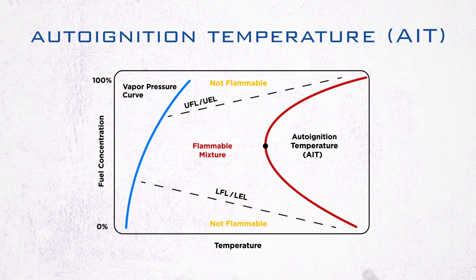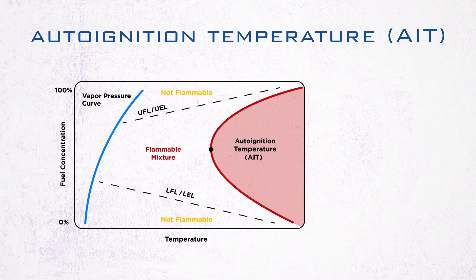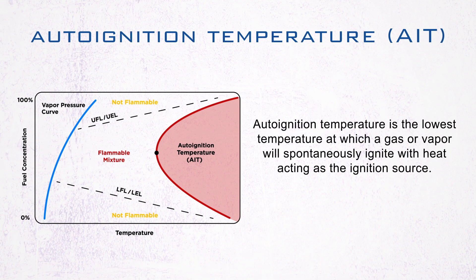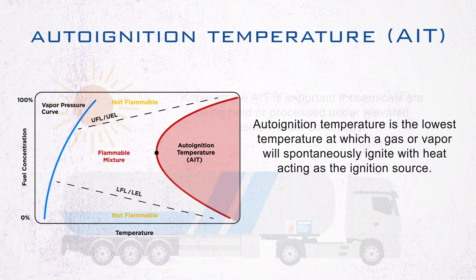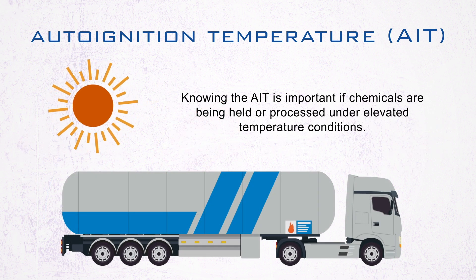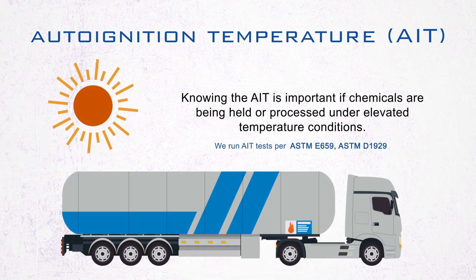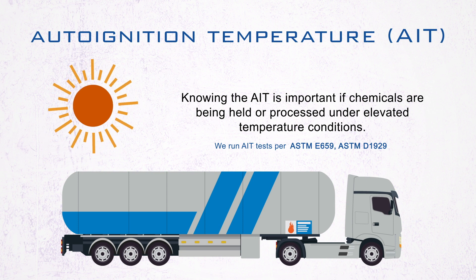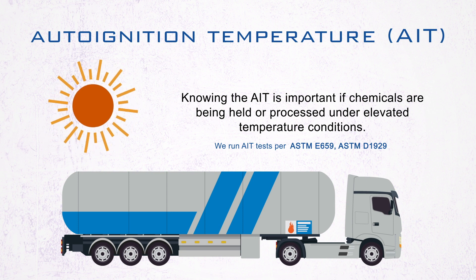Auto-ignition temperature, or AIT, is the lowest temperature at which a gas or vapor will spontaneously ignite with heat acting as the ignition source. Knowing the AIT is important if chemicals are being held or processed under elevated temperature conditions.